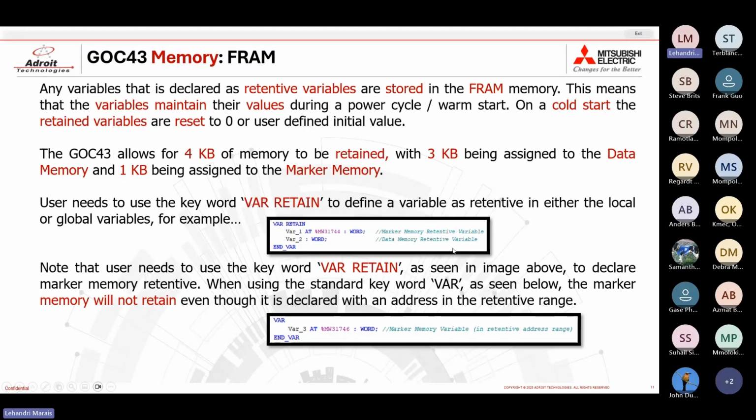So declaring a marker memory outside of the range, even though you use retain, will mean that it won't retain. Similarly, if you don't use the keywords for retain, but use the range for the retentive memory, it will also not retain. So you need to have both var retain as well as the range correct.